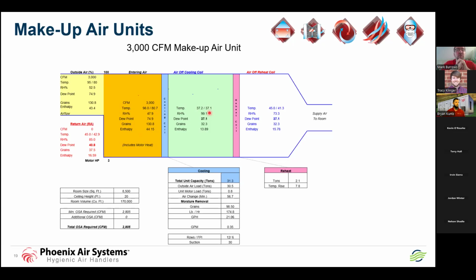Nobody wants 37-degree air to blow down their back. In this case, we take a simple reheat coil. We've already got the air down below the dew point. This is just worker comfort. We take the air from 37.2 up to 45 degrees. And look what happens to the relative humidity. That change from 37.2 heating up to 45 degrees, we change the RH from 99.1 to 73.3. Notice again, you don't change the dew point, and you certainly don't take any grains of moisture out. This is nothing more than we're going to overcool the air, take the moisture out, and then heat the air back up for worker comfort.